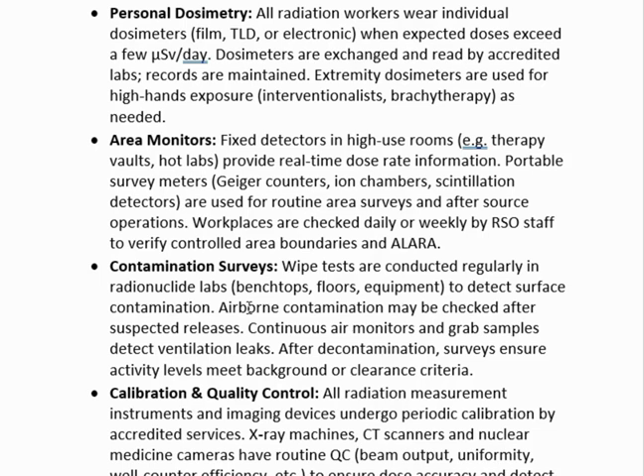Area monitors. Fixed detectors in high-use rooms, e.g. therapy vaults, hot labs, provide real-time dose rate information. Portable survey meters, Geiger counters, ion chambers, scintillation detectors are used for routine area surveys and after-source operations. Workplaces are checked daily or weekly by RSO staff to verify controlled area boundaries and ALARA.